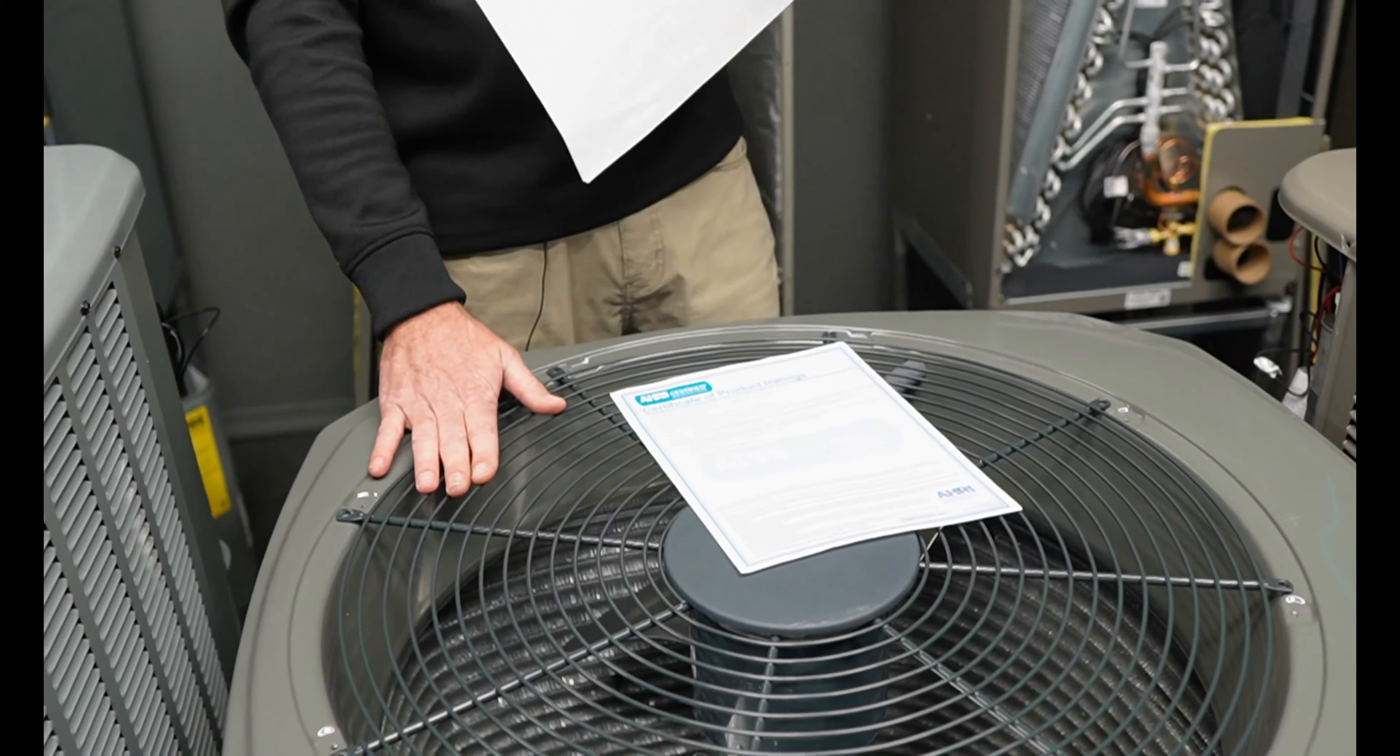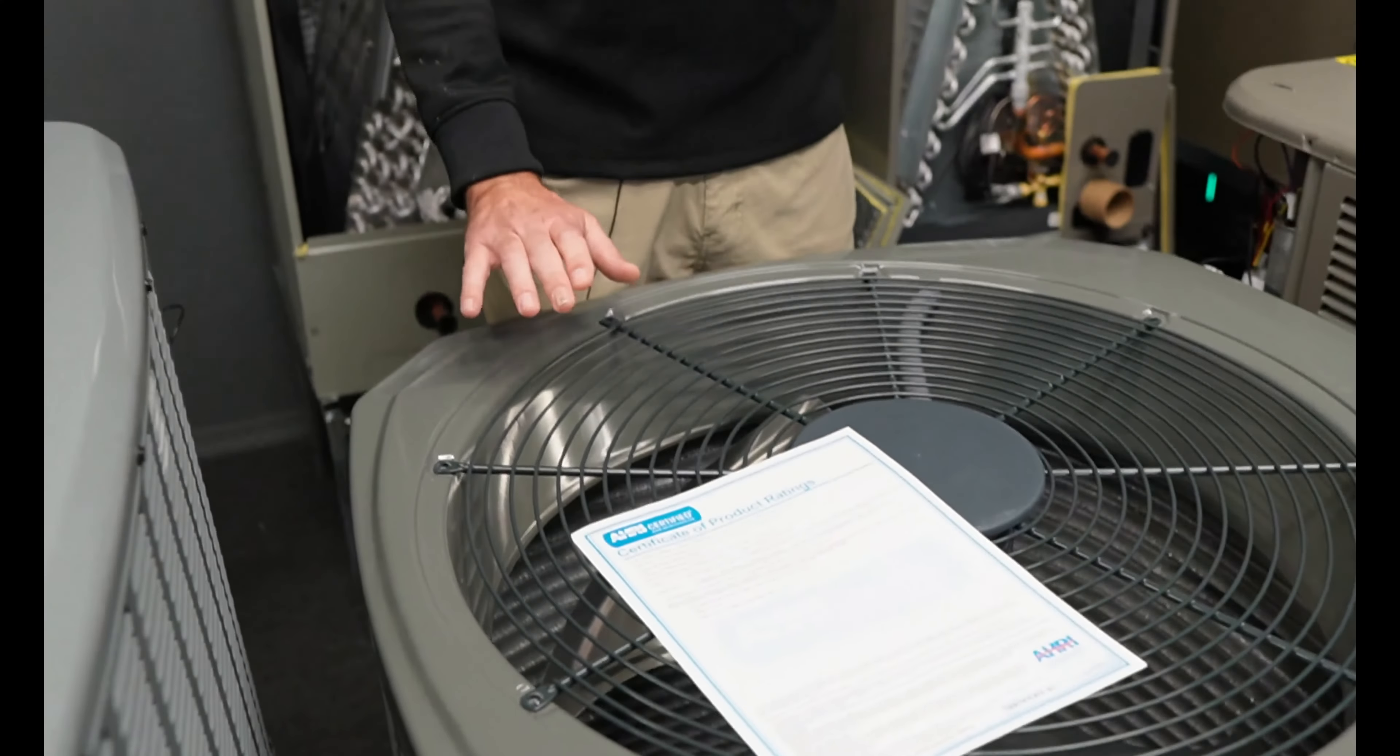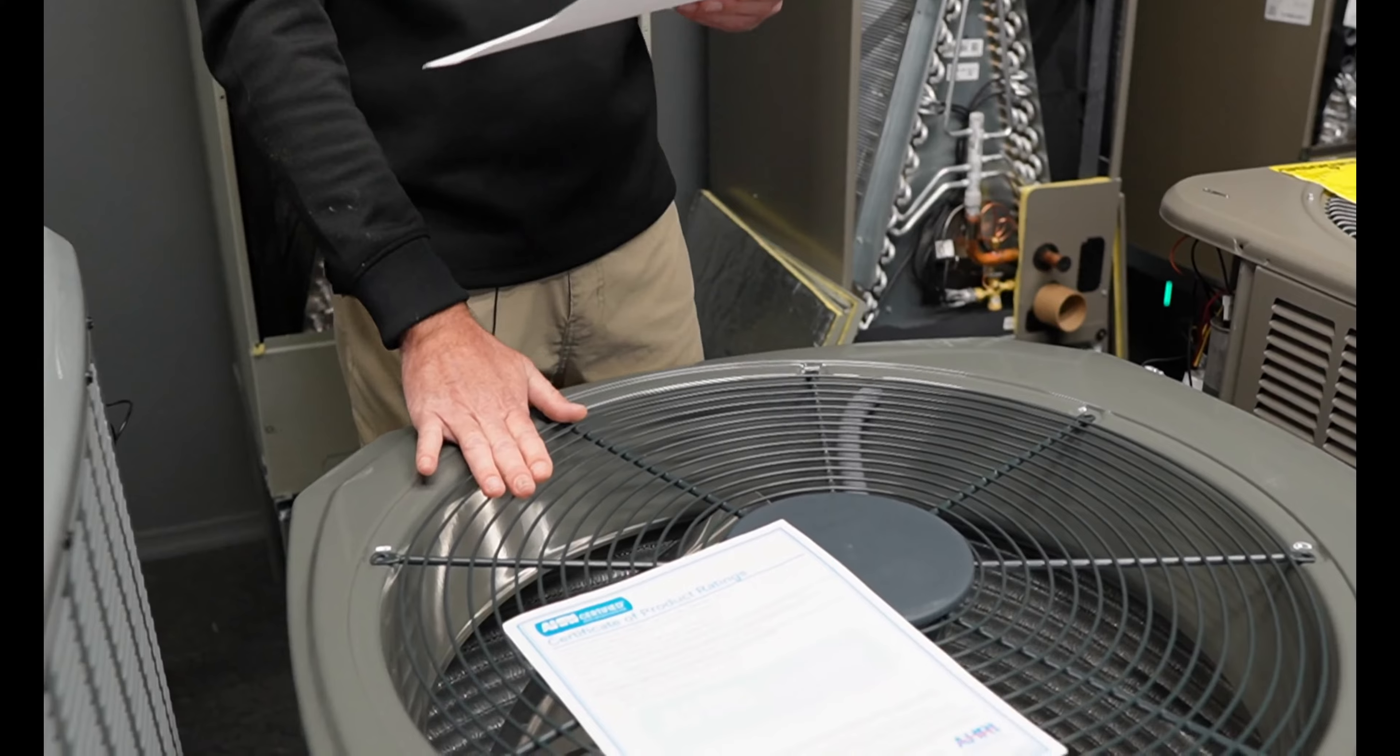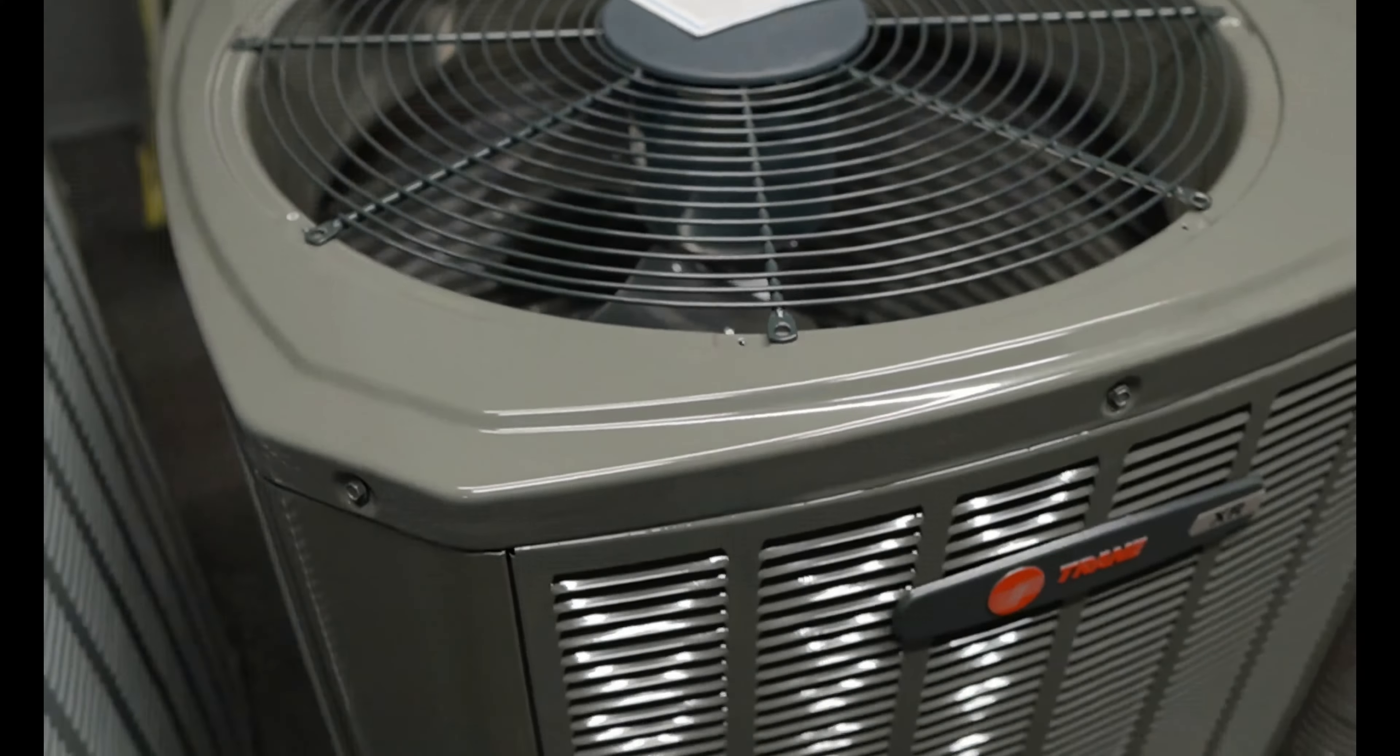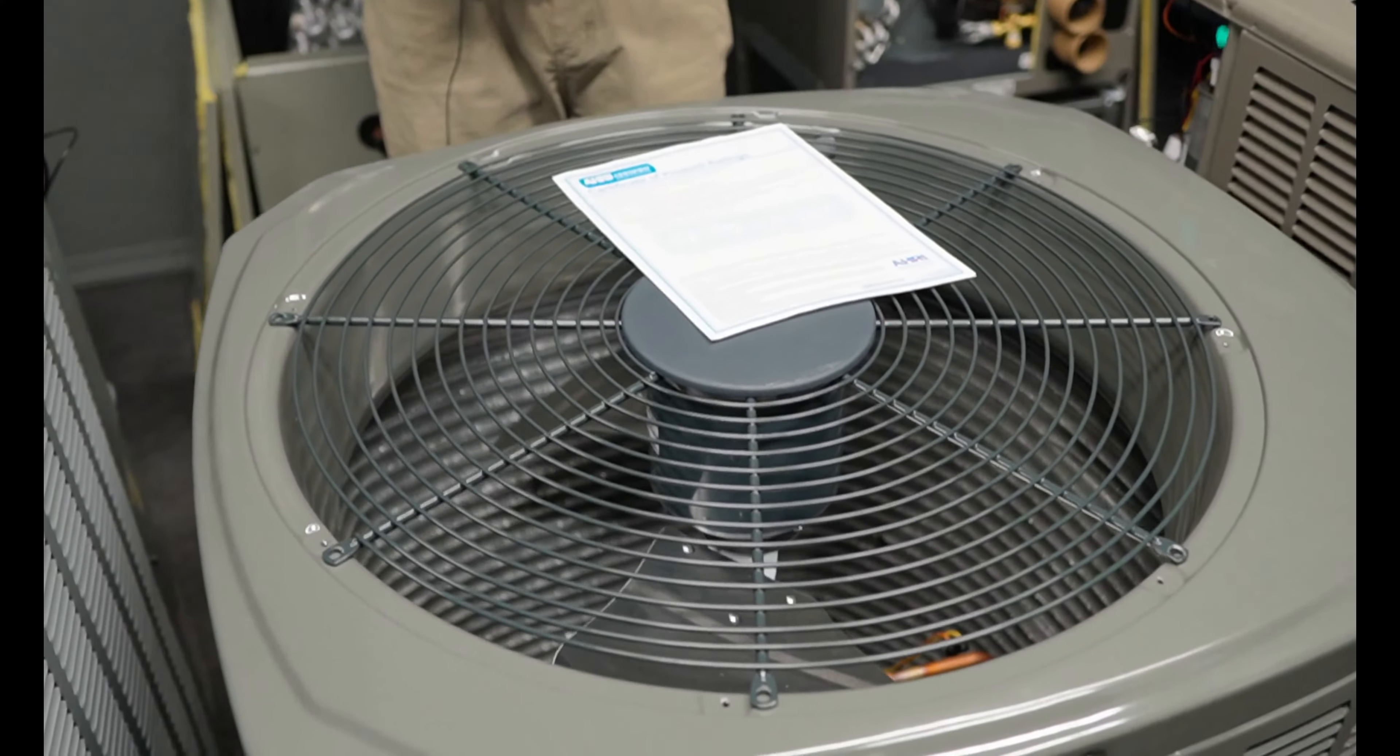I wish I could give it more points for the spine fin. We didn't want to open up the argument, right? The tubing size on that is 3/8, big tubing size, huge. It's going to get 10 points for that. The noise rating on it, rated below 74 decibels. Definitely going to get points for that because it's rated below. It's going to get 10 points for that. Absolutely.